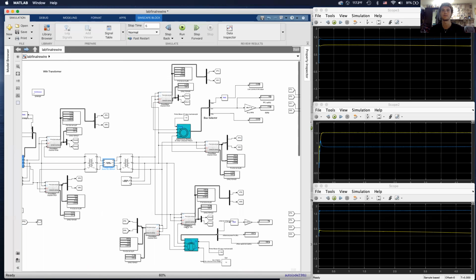A lot of times when you're trying to correct a power factor, you connect some sort of capacitor bank. But it's pretty cool that instead we can use a synchronous motor to do that. I found that for the RPM to not disengage, I had to go to about 1.3 Newton meters before the motor's slip becomes too great.